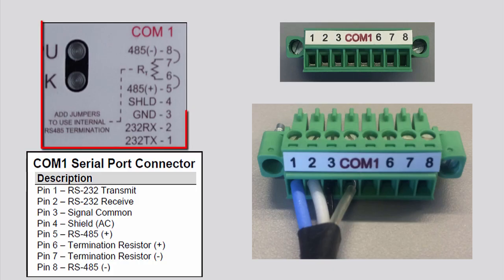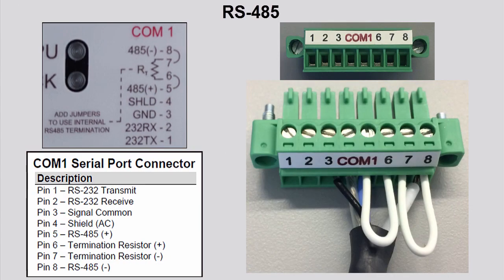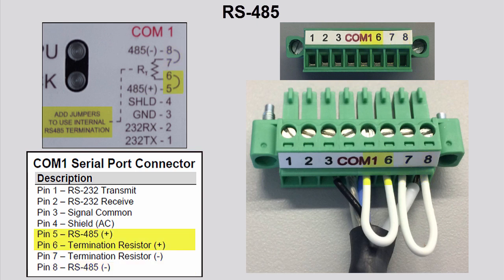Serial connections should be wired according to the chart on the back of the controller. For RS-232, transmit and receive signals are wired to pins 1 and 2 of the connector respectively, signal common or ground wired to pin 3, and shield wire wired to pin 4. For RS-485, positive and negative signals are wired to pins 5 and 8 respectively. Two jumpers — one wired between pins 8 and 7 and the other between pins 5 and 6 — connect the internal 120 ohm termination resistor. There should be a termination resistor on each end of the RS-485 line.